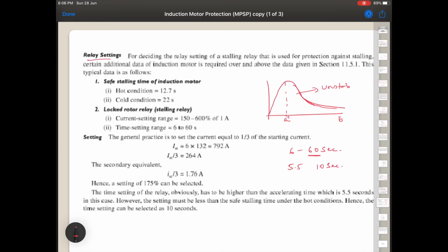So coming to relay settings, for deciding the relay settings of the stalling relay, there are some additional data which are required, that is hot condition and cold condition. These are the safe stalling times, meaning we may expect the motor to come back to synchronism. So we have one more thing called the locked rotor relay, that is stalling.